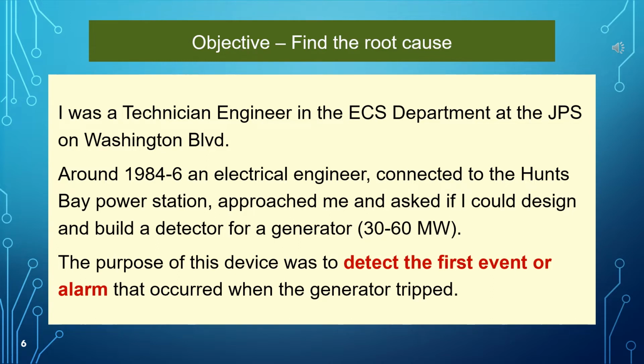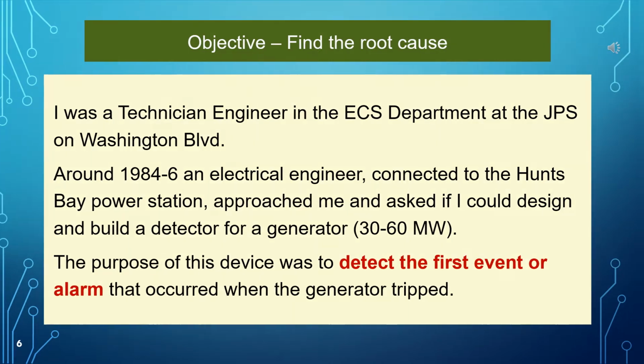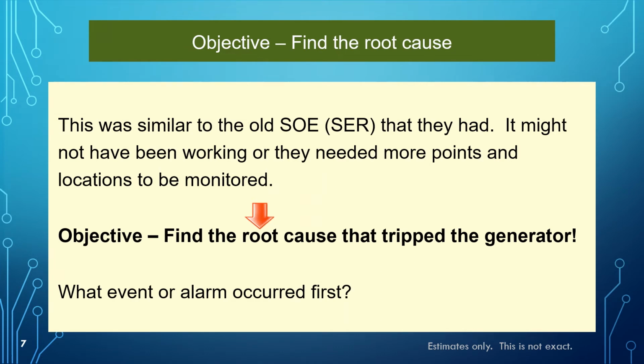The purpose of this is to detect the first event or alarm that occurred when the generator tripped. Find the root cause. This was similar to the old SOE or SER that they had. It might not have been working, or they needed more points and locations to be monitored. Objective: find the root cause that tripped the generator. What event or alarm occurred first?